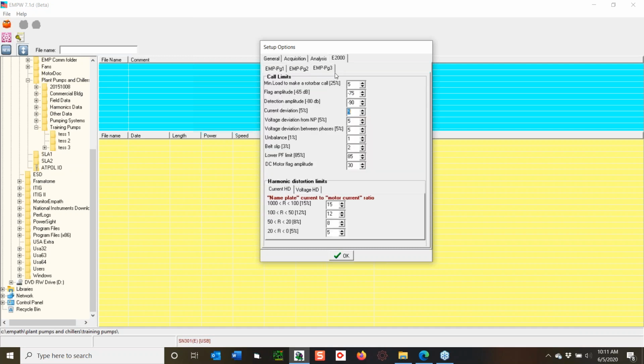And then last but not least, the alarm settings. For minimum load to call a rotor bar, I like to leave that all the way down, because I detect all the time when I have that block setting selected. Now we're taking 12,000 samples a second and a 65,000 block size. That means I have so many lines.